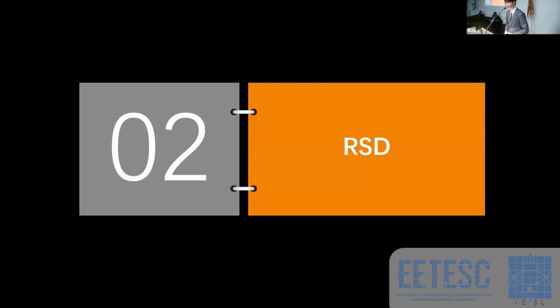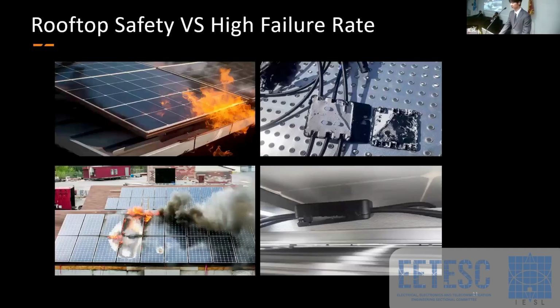Because AFCI provides the intelligence to identify the threat, but the RSD, the rapid shutdown, delivers the physical action to eliminate it. As you can see from this slide, the images show what happens when we lose control of the DC energy on a rooftop. As long as the sun is shining, those modules are active. Without a way to shut them down at the source, a small fault can quickly turn into a disaster, especially for the firefighters.